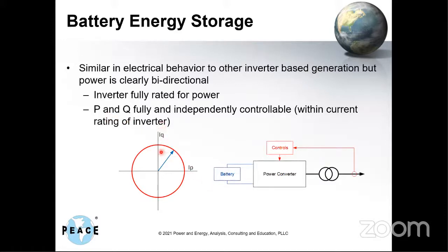So if this is reactive current and this is active current, you can control this thing within this circle, where the circle represents the full current rating of the converter. You can operate anywhere in this region and very quickly go from one point to another. You have full control of P and Q independent of each other, so long as you stay within this circle. Now, when you hit the circle, you can have either active or reactive priority. That's something you may have heard from many vendors. What that means is during, say, for example, a fault or some event, they give priority to reactive power or active power, depending on your grid code.